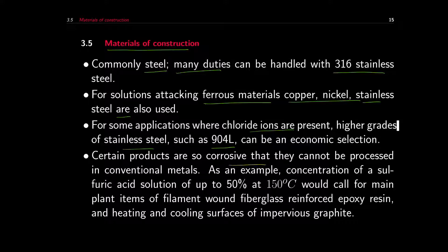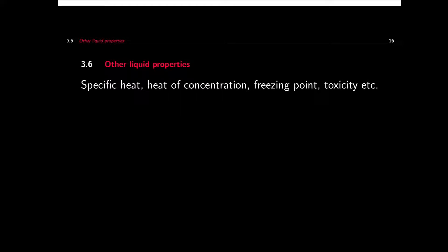Certain products are so corrosive they cannot be processed in conventional metal. For example, for concentration of sulfuric acid up to 50% at 150 degrees Celsius, we need to use filament-wound fiberglass reinforced epoxy resin for the main plant items, and the heating and cooling surfaces should be of impervious graphite. Other liquid properties that affect the operation and design of evaporators are specific heat, heat of concentration, freezing point, and toxicity.